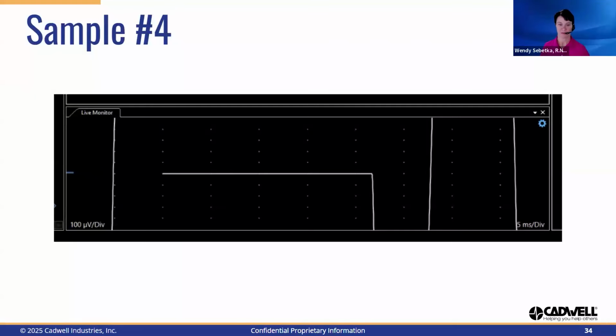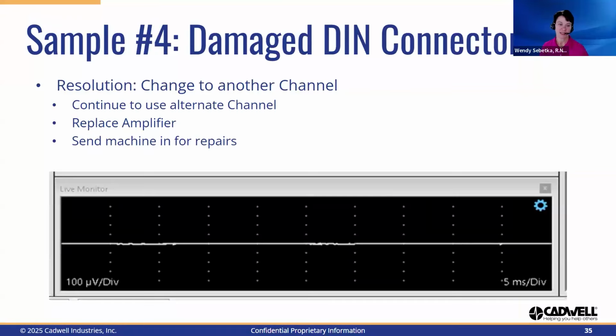Electrode and patient management techniques failed, so we proceeded to the machine management techniques. Machine settings were configured to use a different channel and the issue was resolved, confirming this specific scenario was an issue with the DIN connector. The alternate channel was continued to be used until the amplifier could be sent in for repair or replacement.